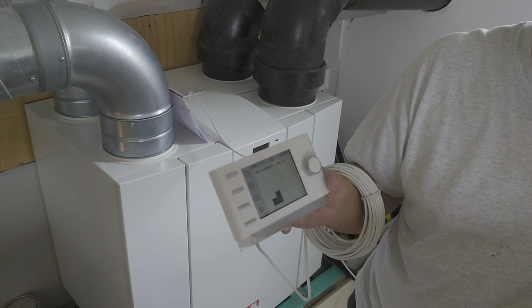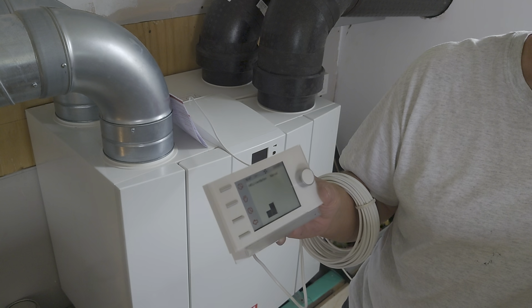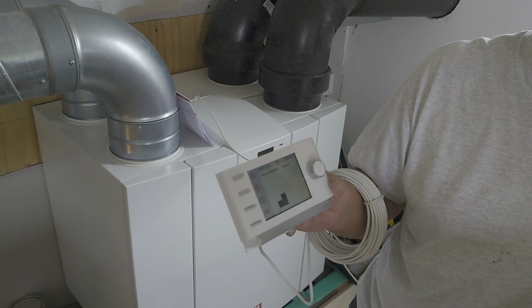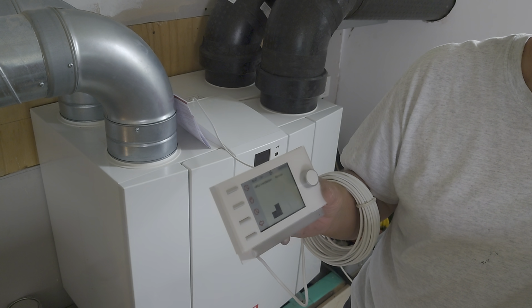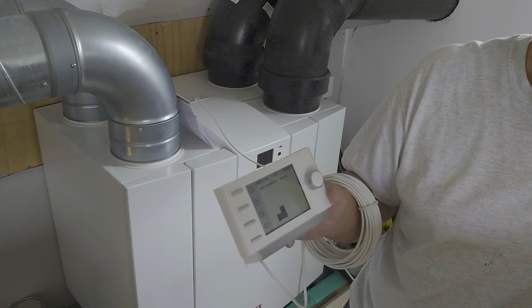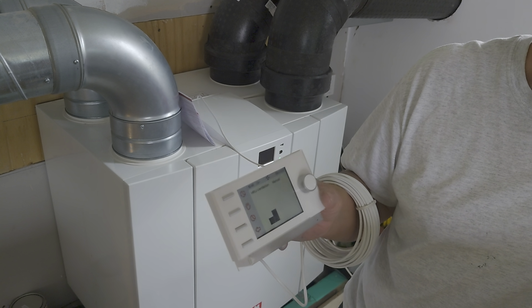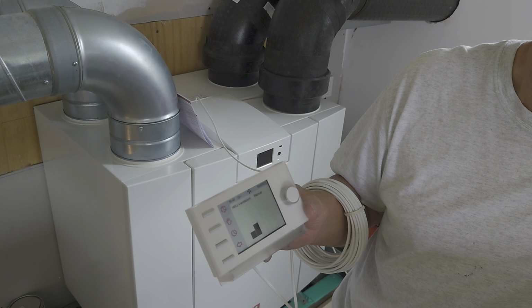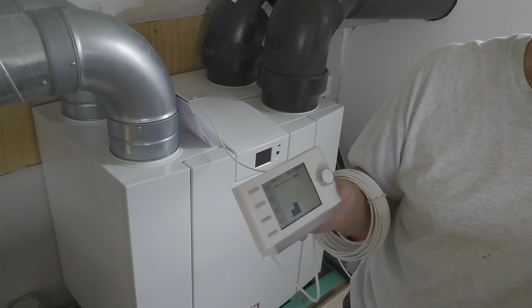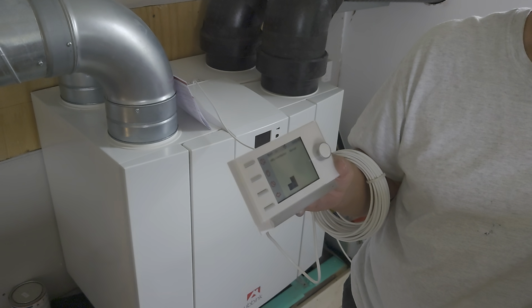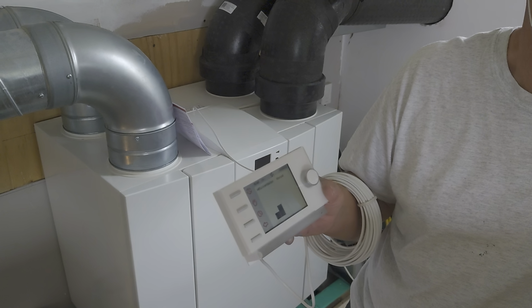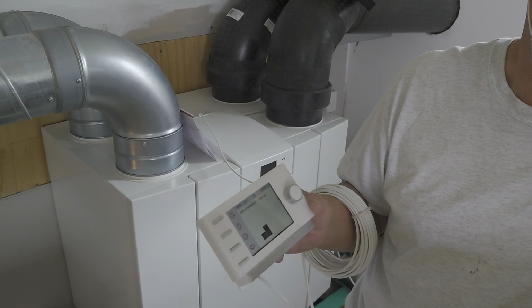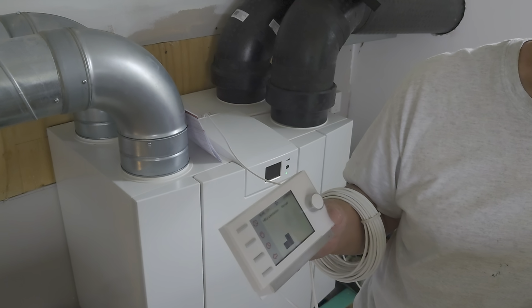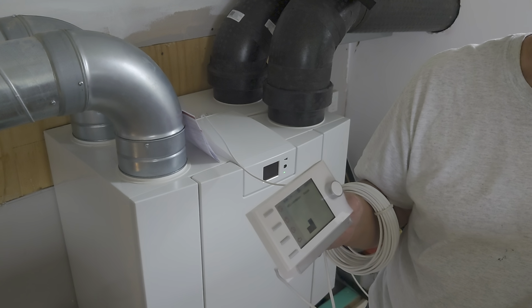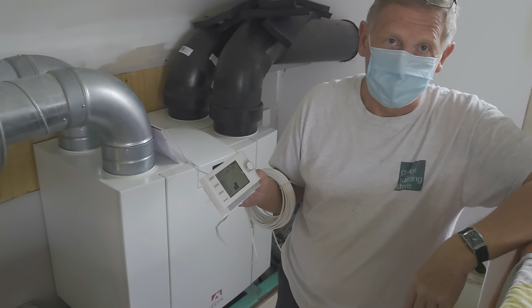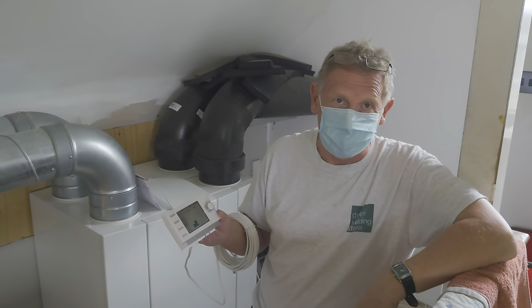Now, in winter, one side of the heat exchanger is a warm, damp environment. So if you turn the airflow off for any significant length of time—really talking months, not a few days or a couple of weeks—you could get mould growing inside the machine as well. Even though the air is filtered, it's not filtered down to microbe level, it's just filtering dust. So any sort of microbes or whatever from dead skin will find its way into the machine.